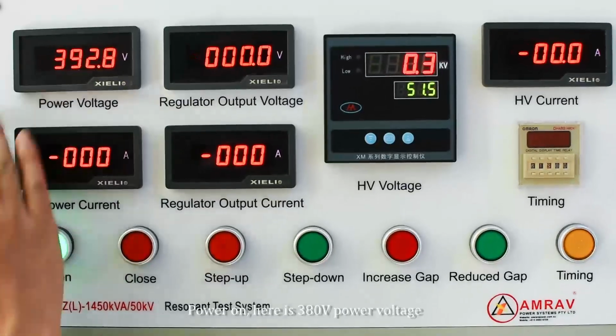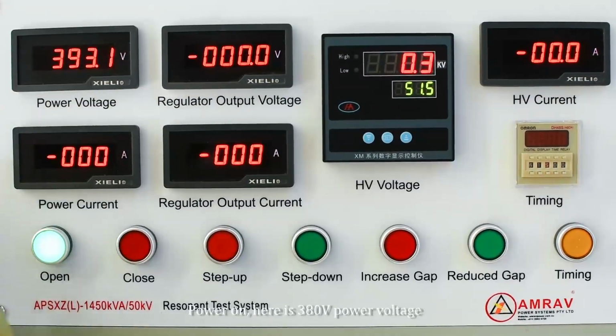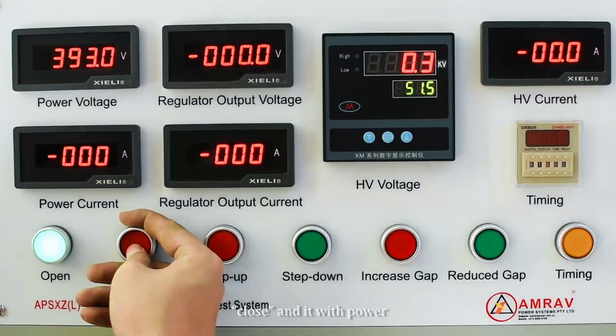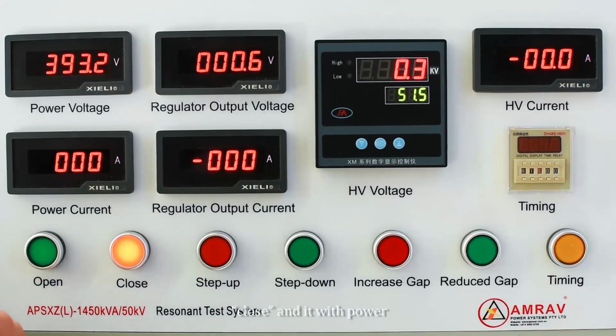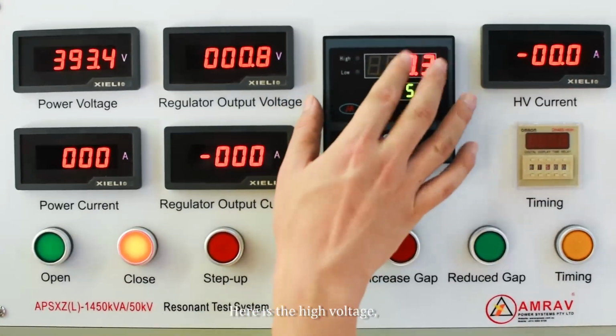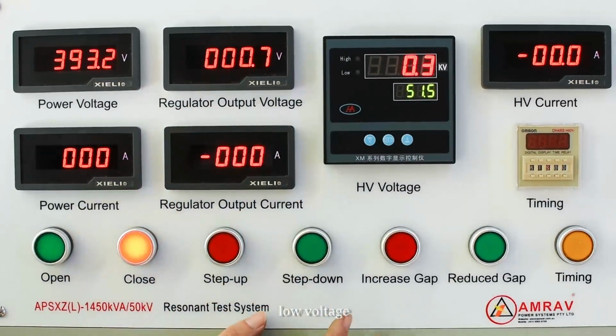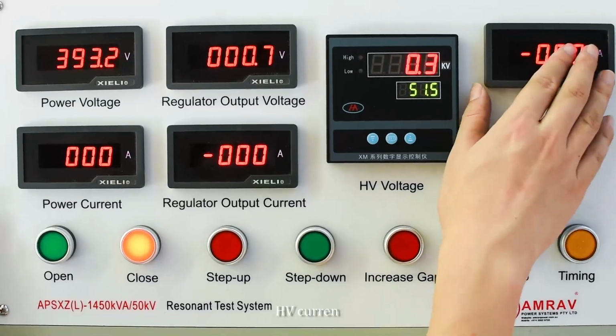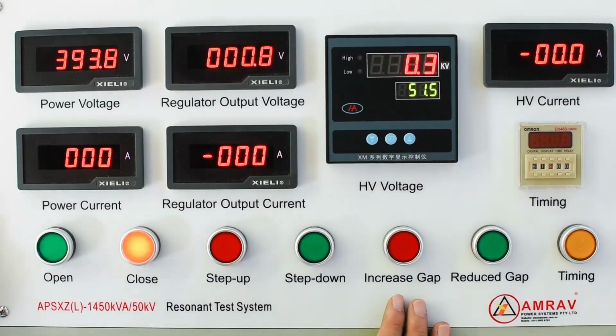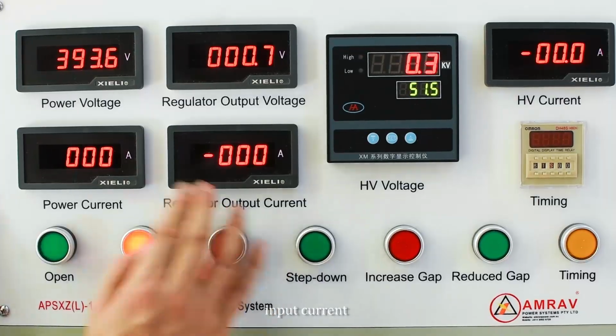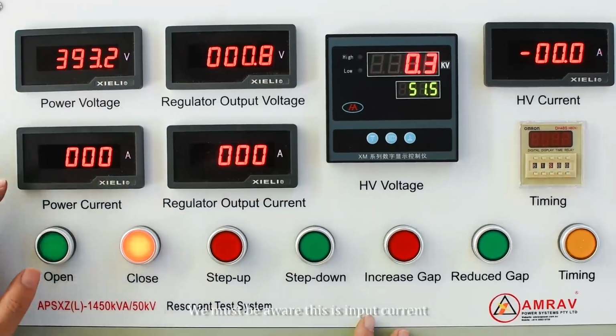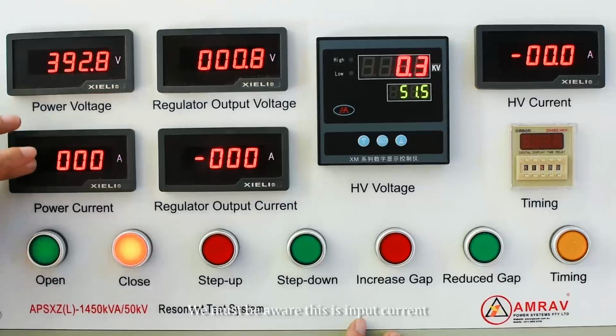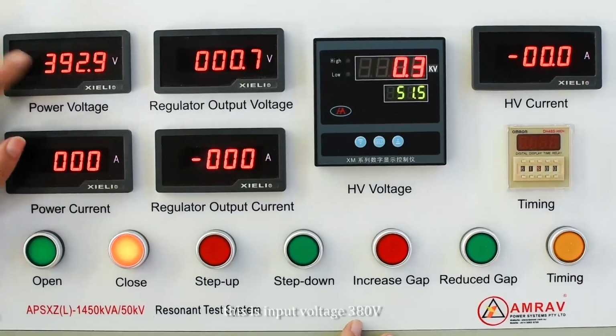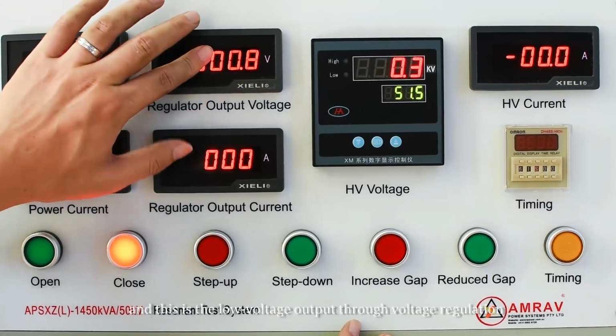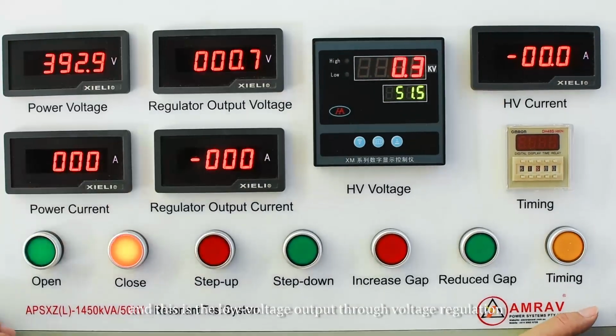Power on. Here is 380 volt power voltage. Close it and power up. Here is the high voltage, low voltage, HV current, output current, input current. We must be aware this is input current. This is input voltage 380 volt. And this is the low voltage output through voltage regulation.